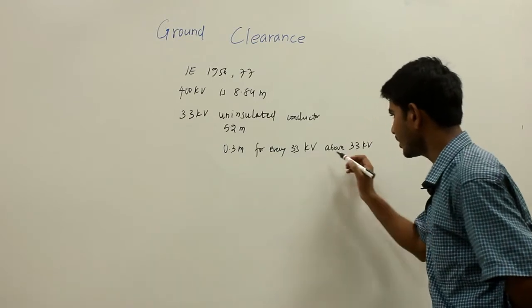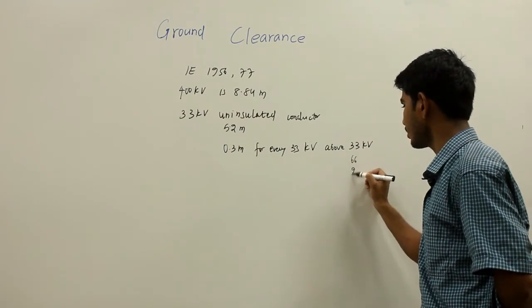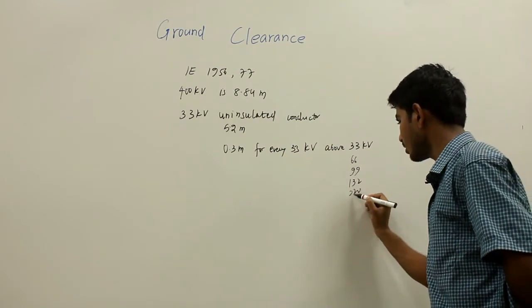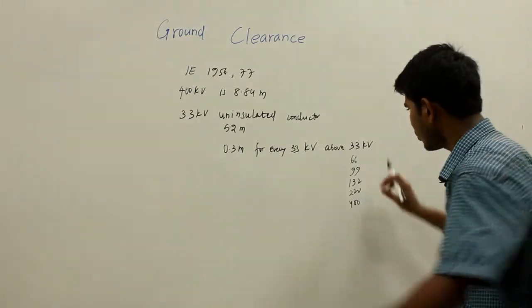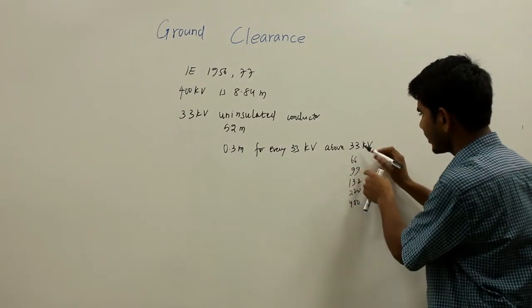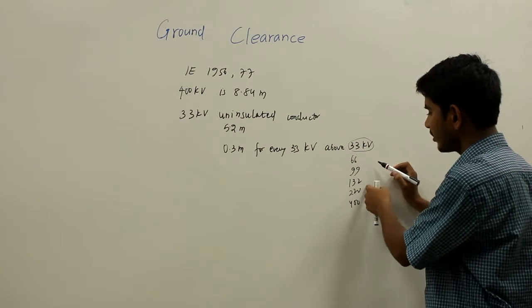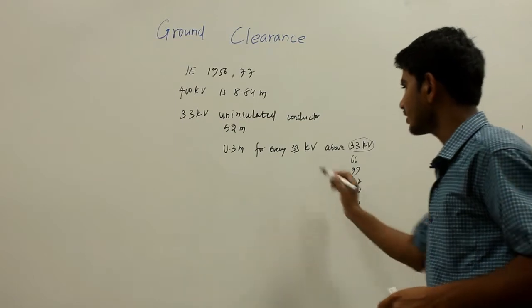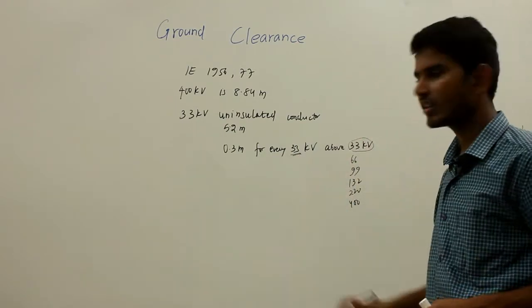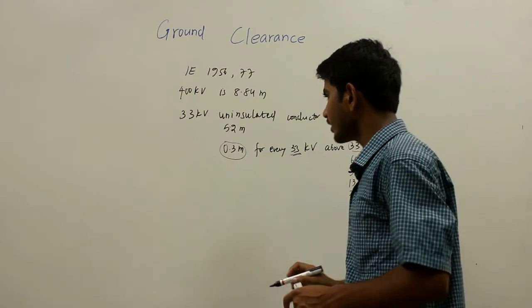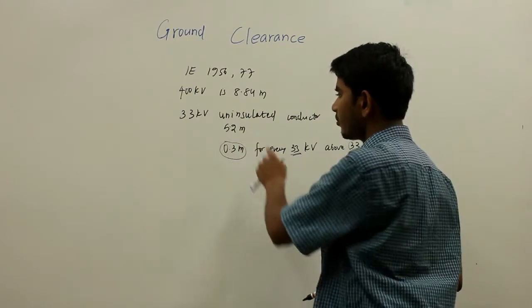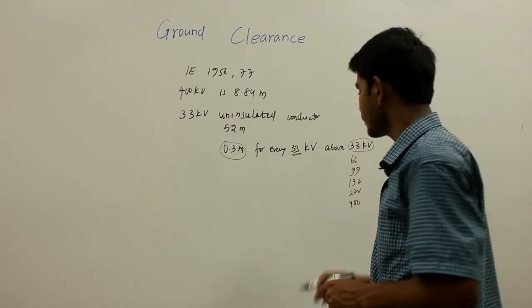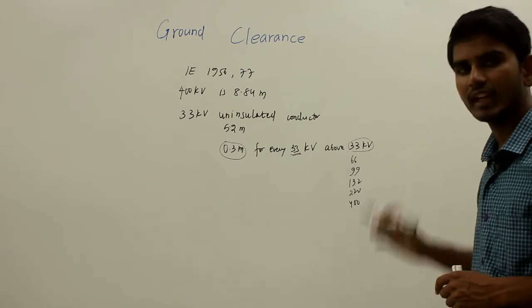That means, for any given voltage level — whether 66, 99, 132, 220, or 400 kV — I will subtract 33 kV from that voltage, then divide the result by 33, so that I can multiply the result with 0.3 to know the clearance to be added to the base 5.2 meters. Ultimately, I can find the minimum ground clearance for that particular kV transmission line.